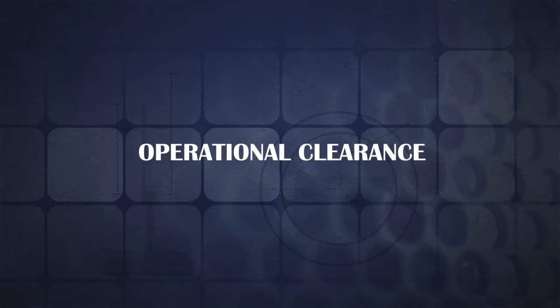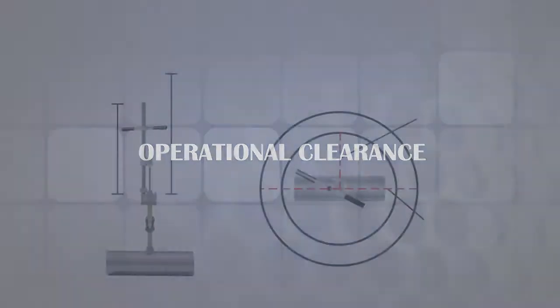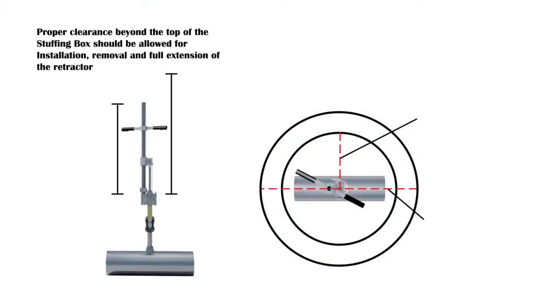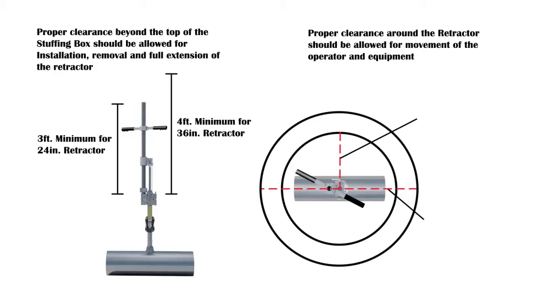Operational clearance. Proper clearance beyond the top of the stuffing box should be allowed for installation, removal and full extension of the retractor. A minimum of 3 feet clearance when using a 24-inch retractor and a minimum of 4 feet clearance when using a 36-inch retractor. Proper clearance around the retractor should be allowed for movement of the operator and equipment.